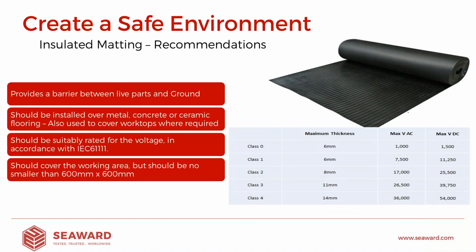Once we've created a bench, or if we need to create an insulated top, we should then look at things like insulated matting. Now again, insulated matting could be used on top of a bench, but more commonly it's involved in putting on the floor to create that barrier between the operator and the ground. So you should always look to install this, particularly if you have metal, concrete, or any kind of ceramic flooring. And again, as I discussed, it can also be used to cover worktops.